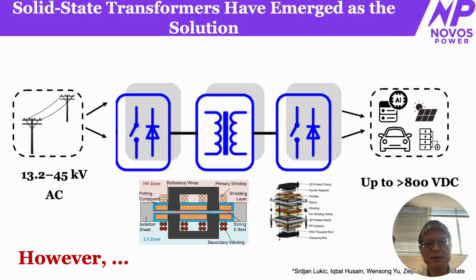That has led us to look for new solutions. One technology is a solid-state transformer, or SST. SST eliminates the need for a traditional low-frequency transformer, and it incorporates a high-frequency isolation transformer to minimize size, decrease weight, increase efficiency, and increase redundancy. The bottom of the diagram shows the transformer design for our current isolation transformer in SSTs, and that imposes a number of issues.